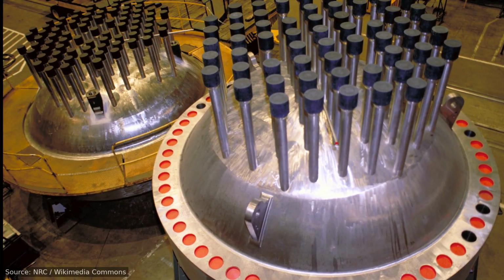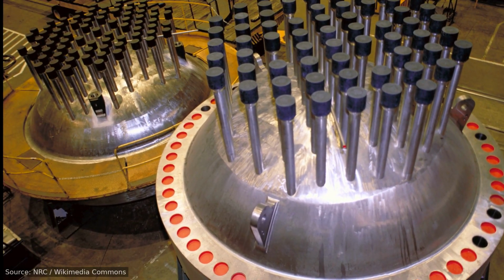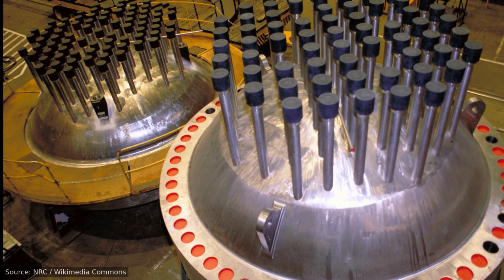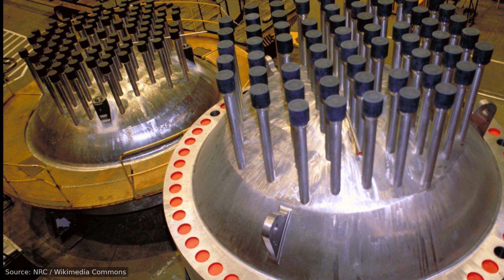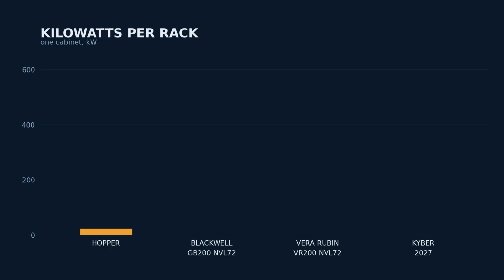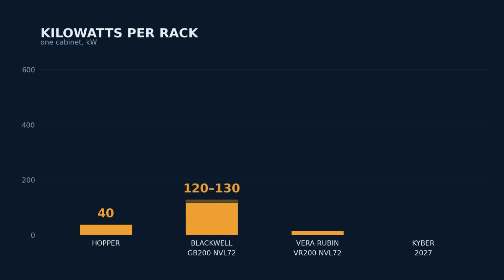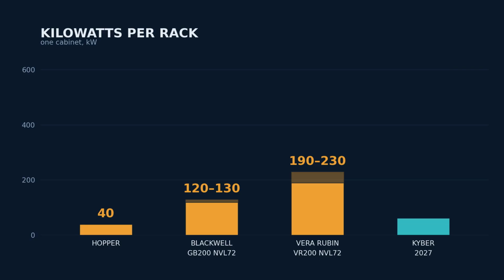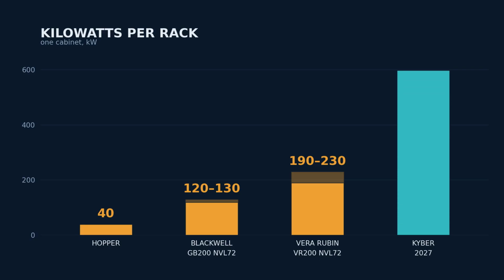The difference is everything around it. A reactor is built from the ground up around that heat. The chip is a part you slide into a rack. Now stack the parts. A Hopper-era rack drew around 40 kilowatts. The Blackwell generation moved that to 120, 130. The rack shipping later this year sits between 190 and 230 kilowatts. The generation after it is planned at around 600 kilowatts in one cabinet, the width of a wardrobe.